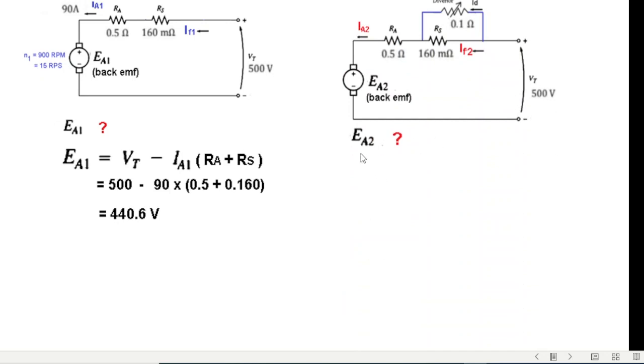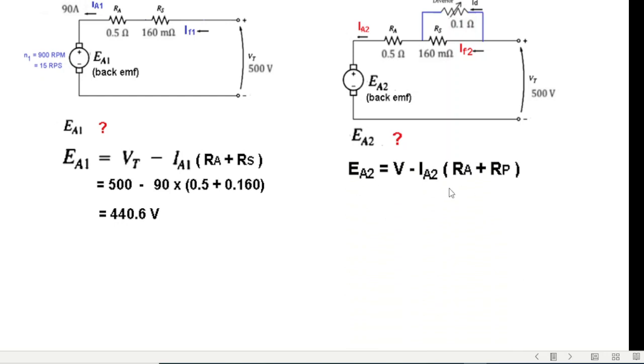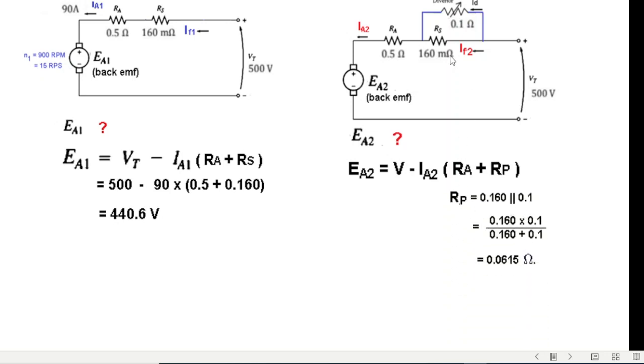For EA2, the equation becomes EA2 = VT − IA2·RA − IA2·RP, where RP is the parallel combination of the field resistance and diverter. RP = (0.16 × 0.1)/(0.16 + 0.1) = 0.0615 ohms. We now have RA and RP, but IA2 is unknown and must be calculated first.